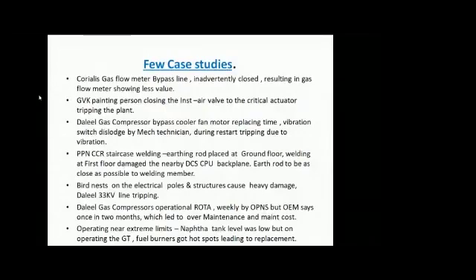So now coming to another point, which is welding. Welding is another issue where people have to be very careful, especially during construction there's no problem, but during operation and maintenance time, whenever welding is done, it has to be ensured that the welding rod, the member, and the earthing should be very close to each other. Otherwise, it will cause circulating currents that will damage electronic components.